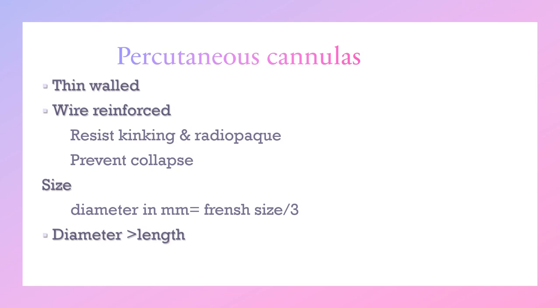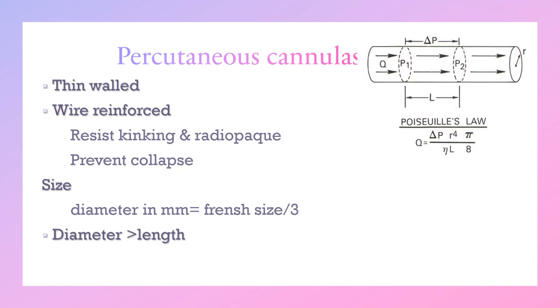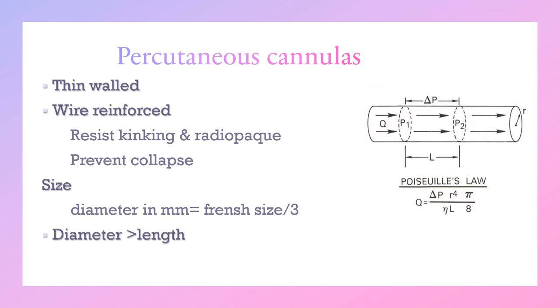The size of the cannula refers to the outer diameter, which can be expressed in French units — each 1 mm is equal to 3 French. The diameter of the cannula is very important in determining flow, more so than the length. Based on Poiseuille's law, flow is proportional to the 4th power of the diameter. Even cannulas of the same size from different manufacturers can have different flow and pressure drop characteristics.